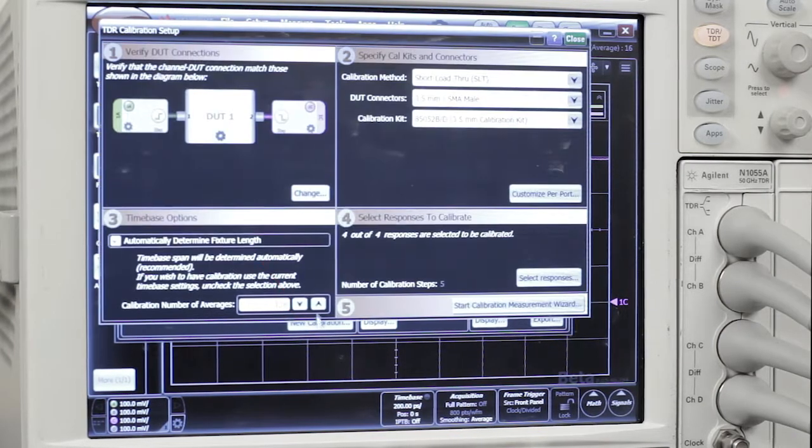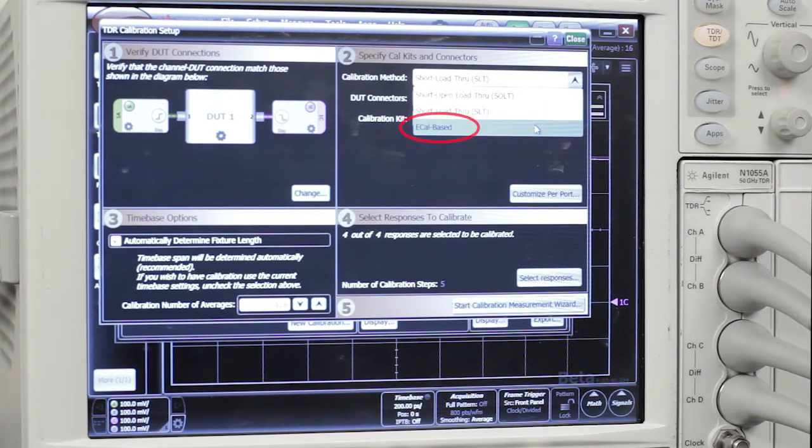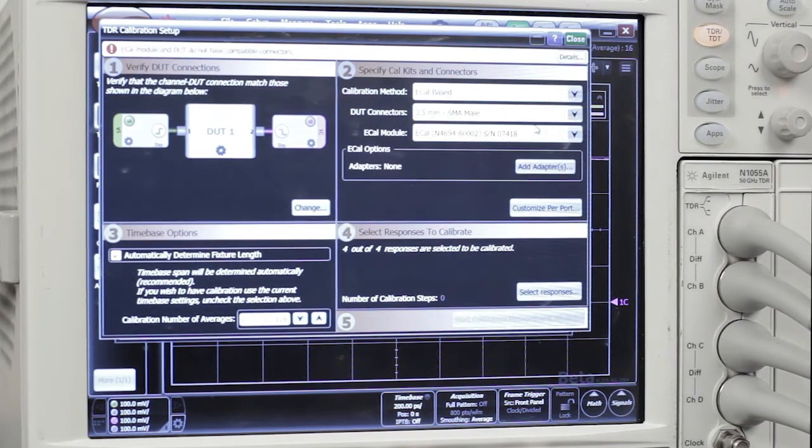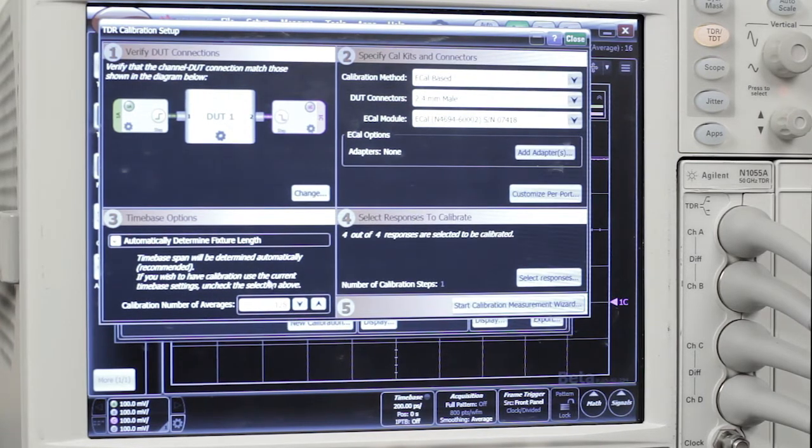So we can select a new calibration. There's several steps here. The first one is to just confirm the setup is what you want, and it is. Then you have a choice on the type of calibration you're going to do. Today we're going to do ECAL, so we select that. We have to answer some questions about the type of connectors on our DUT, and we have 2.4 millimeter males. We set up the averaging we want, and that's good, and then we can start the calibration measurement wizard.